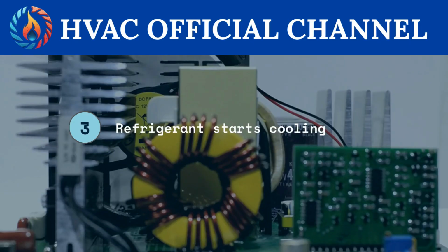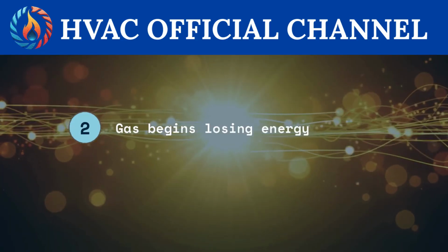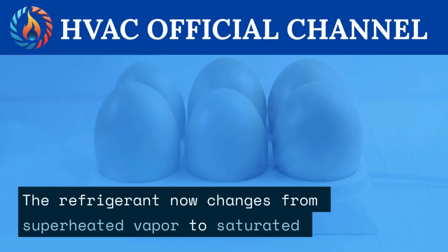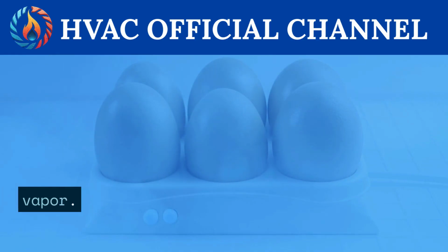Step 3. Refrigerant starts cooling. As heat leaves the refrigerant, temperature decreases, and the gas begins losing energy. The refrigerant now changes from superheated vapor to saturated vapor.